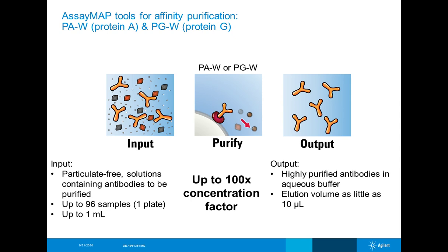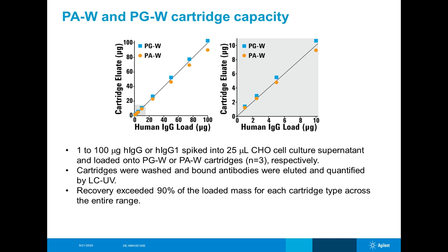Now I'll dive into the workflows. The first is affinity purification using protein A or protein G cartridges. It's very simple: bind, wash, elute. You can use up to 1 mL of your sample — it needs to be particulate-free so you don't clog the frits. Up to 96 samples can be processed. You can elute in as small as 10 microliters, so if you use 1 mL of sample and elute in 10 microliters, you've achieved a 100-fold concentration of a highly purified antibody in aqueous buffer ready for downstream workflows.